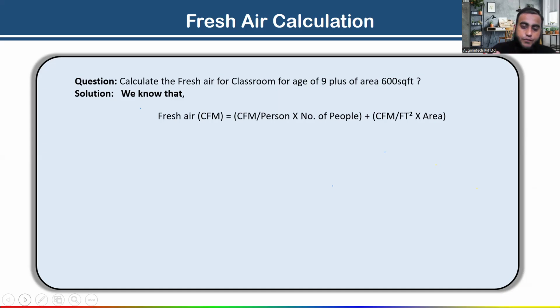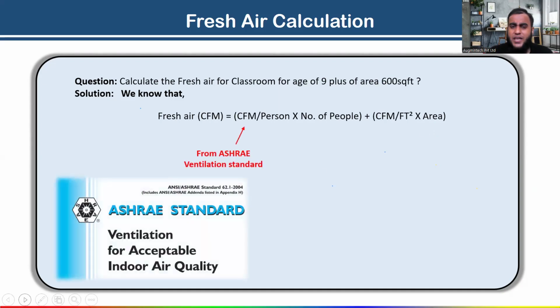Now the question is, sir, from where do we get this value, outside air or CFM per person? CFM is the unit; I am talking about outside air. So from where do we get the CFM per person value? Yes, anyone? From the same ASHRAE 62.1 ventilation standard, you will get the CFM per person value based on your space type, which type of space you have. If you have a classroom, you will get the value accordingly, whatever space you have: office, dining, any space. I will explain that. So the CFM per person value you will get from the ASHRAE ventilation standard.